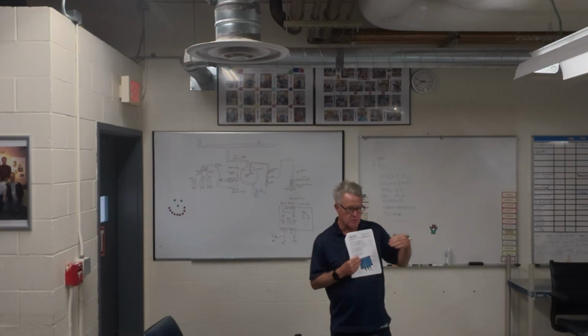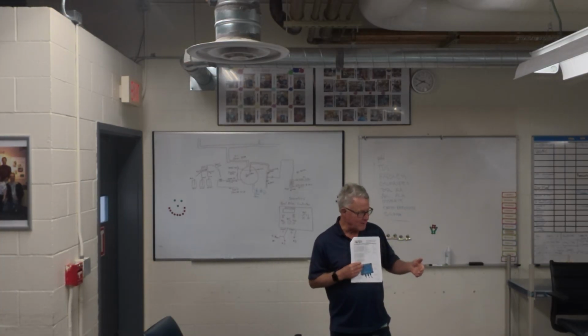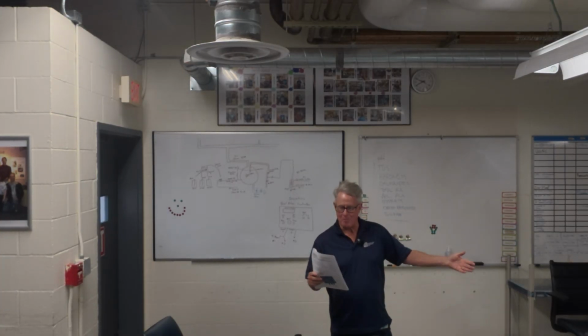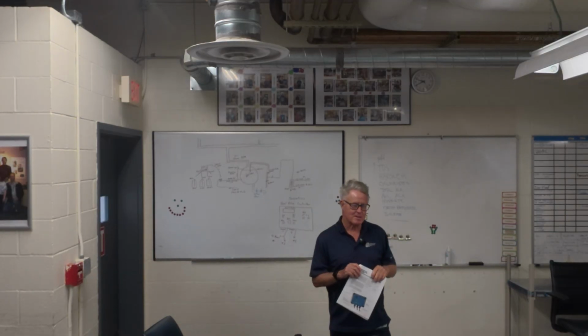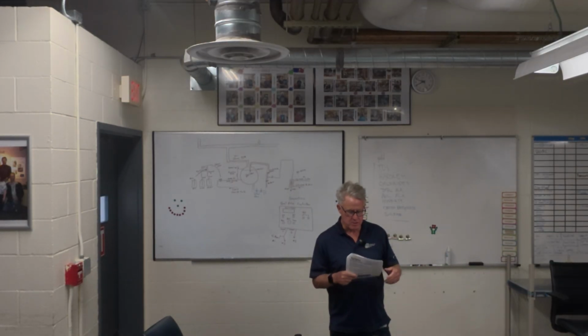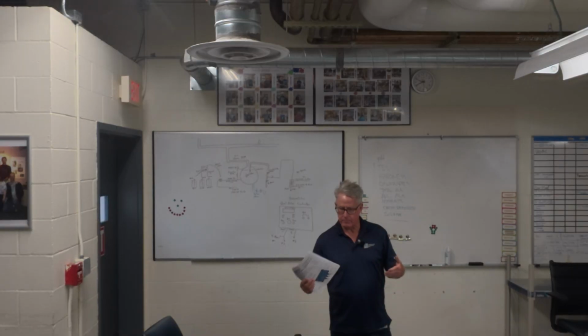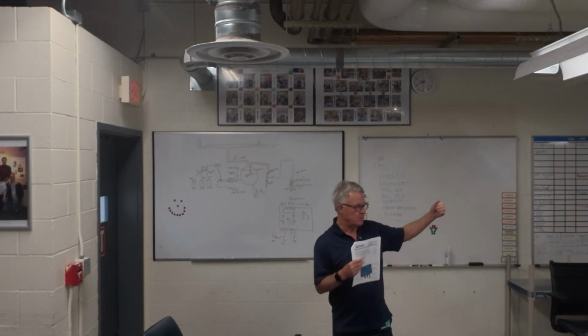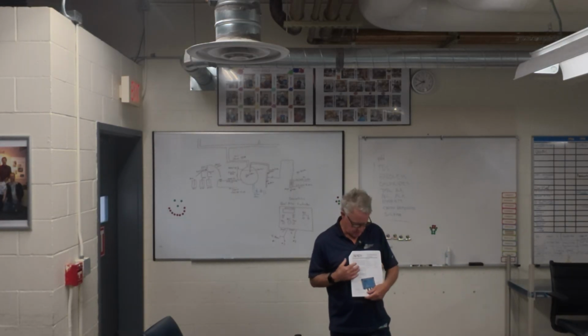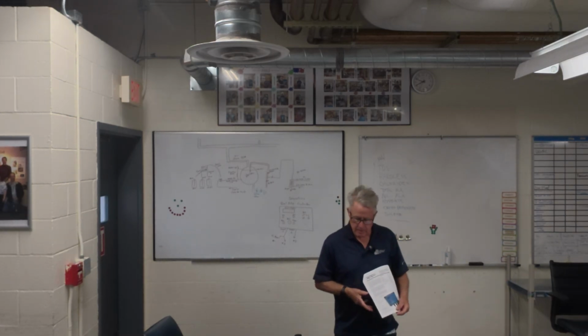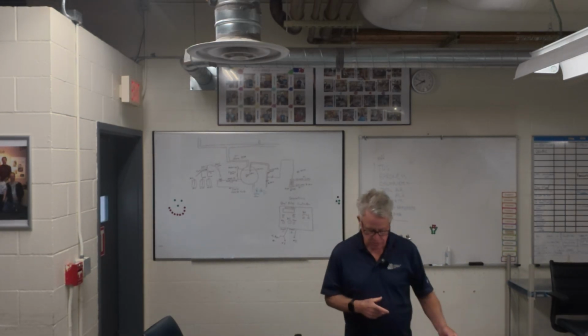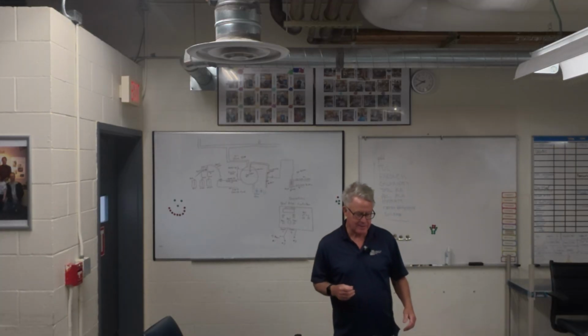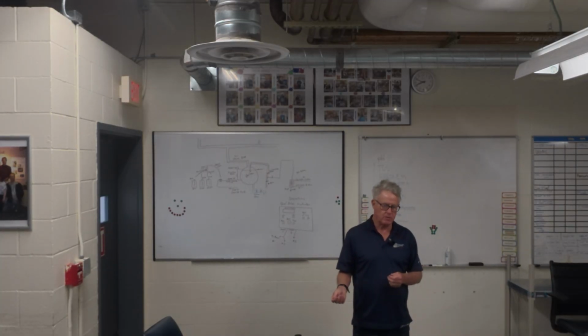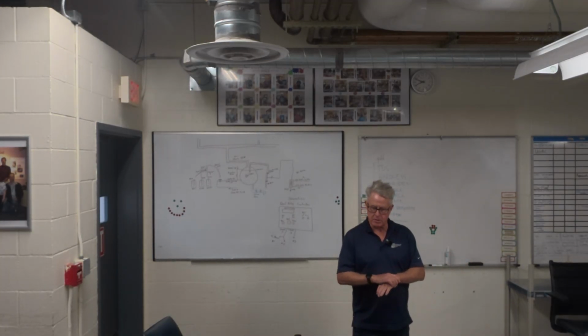That makes sense. So the downside of this is if you forget to do that, we're back to trying to lock it all back down again. So always when you do go through an inspection or drain a boiler, make sure you add 5 gallons in 3 or 4, 10 gallons in 1 and 2. And that'll start to lock the controller down. Other troubleshooting things. I like to think the system's pretty much error-free. We have a lot of places that use this, and it's very successful in locking down and modulating the feeds.